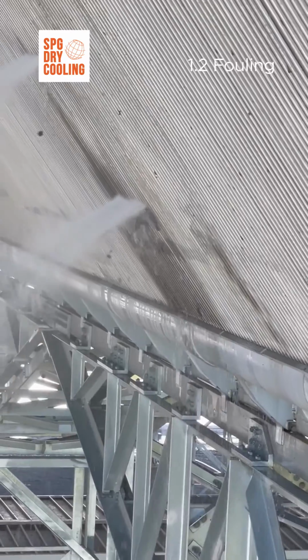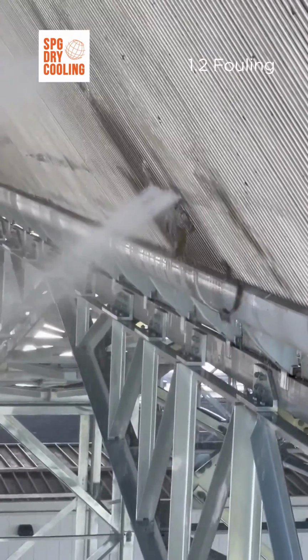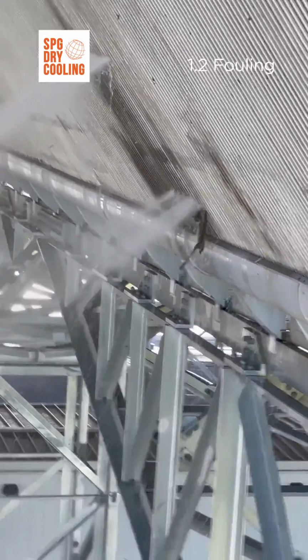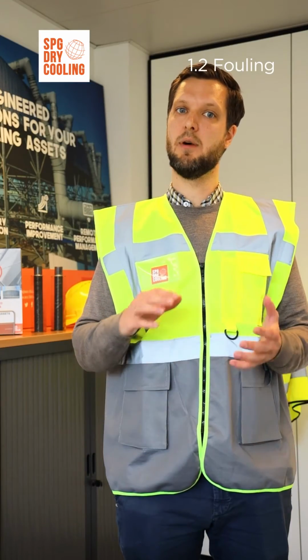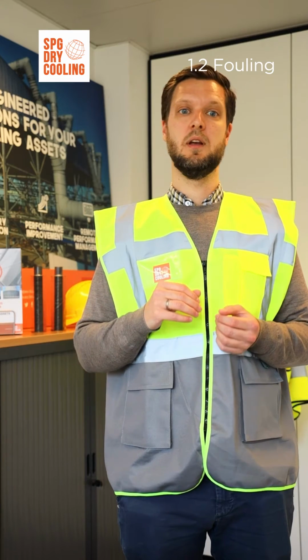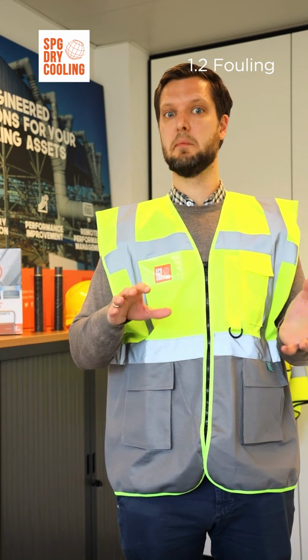You therefore need to regularly clean your ACC to avoid such performance losses. Even worse, if you don't perform regular cleaning of your ACC, the fouling layers become hard and removing them will eventually become impossible. So your bundles will become irreparably damaged and you have to replace them.